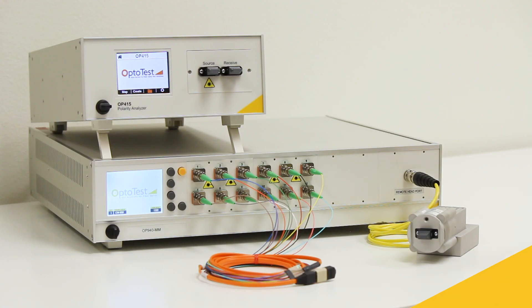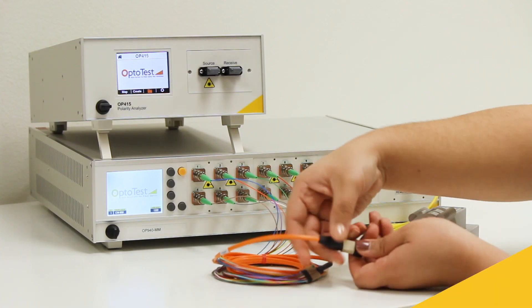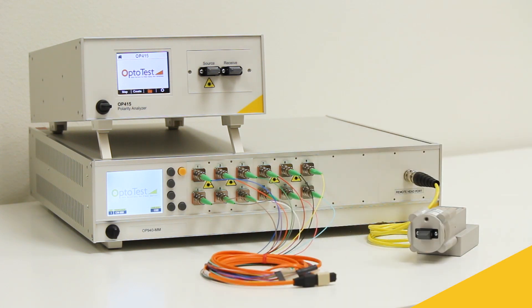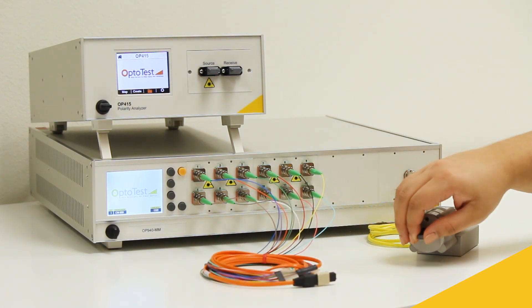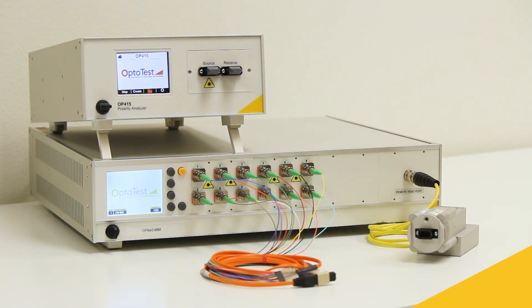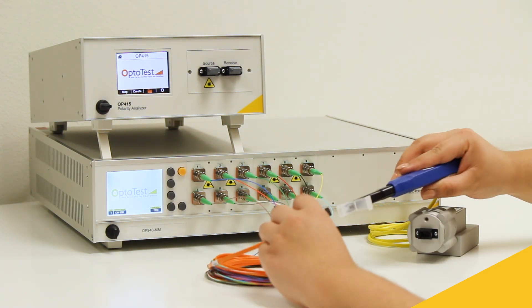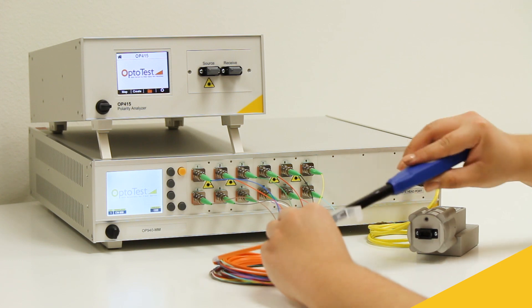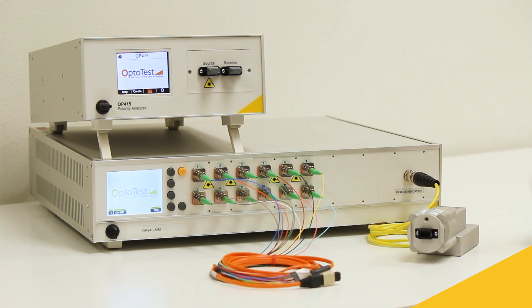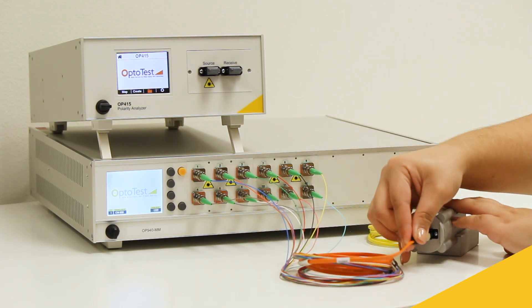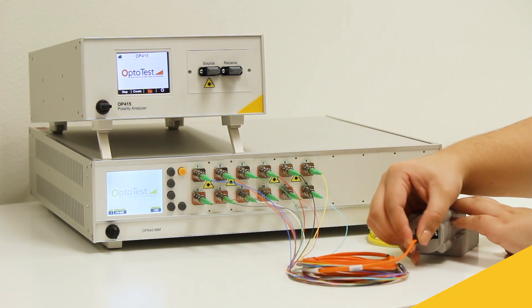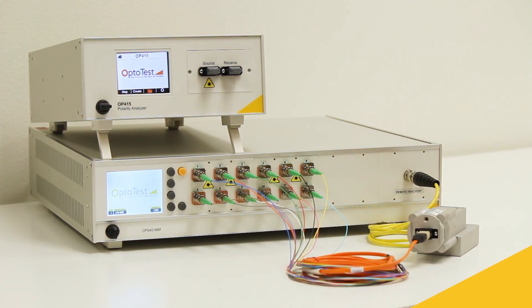Before we start the insertion loss reference, we connect the open end of the fan-out to the detector. Specifically, we connect to the integrating sphere that allows us to use one detector to capture light from all 12 fibers of the MTP cable.